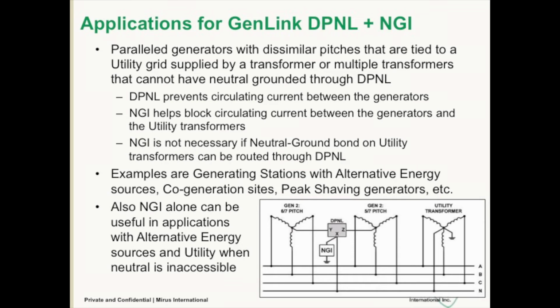Again, if you're able to route the neutral, the best configuration is to take the neutral from the utility transformer and run it through the DPNL. And in this case, you would do a cascaded system. You'd put another DPNL here, and you would run that ground through. That's the best configuration that provides the highest impedance to circulating currents with the lowest influence on the ground fault systems.